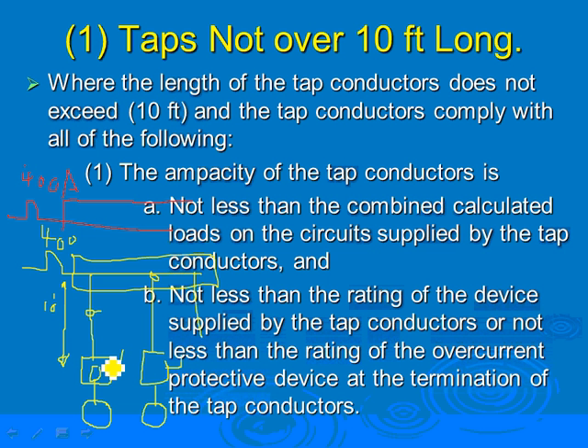The one I want to start with is the minimum conductor that you can tap from a 400 amp, which is 1/10. So what's 1/10 of 400? 40 amp. So this conductor cannot be less than 40 amp. And what's 40 amp? Under 75, that will be number 8. So that conductor cannot be smaller than number 8, period.